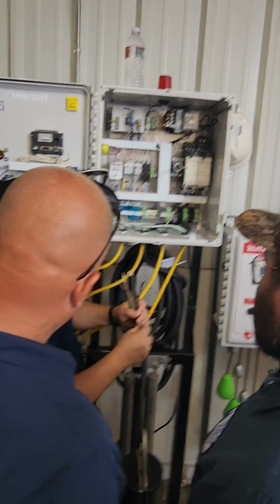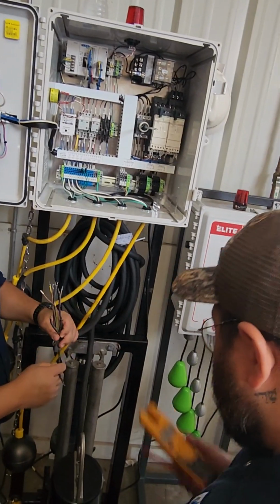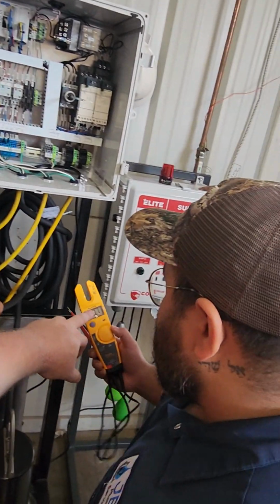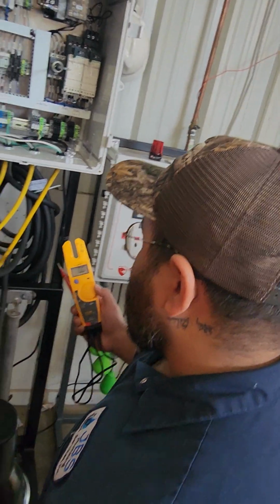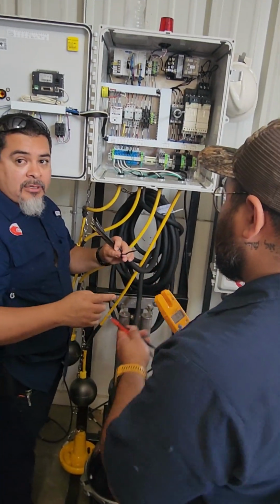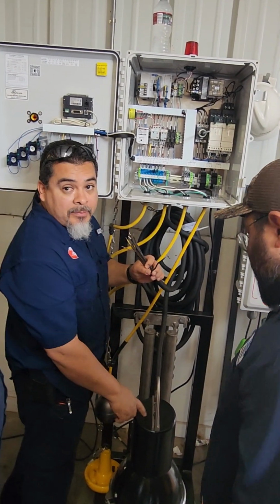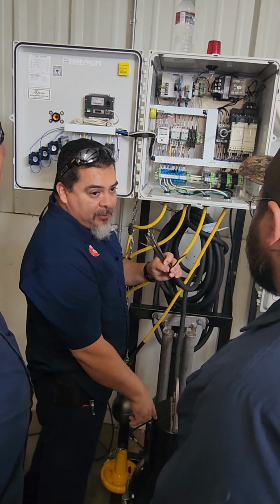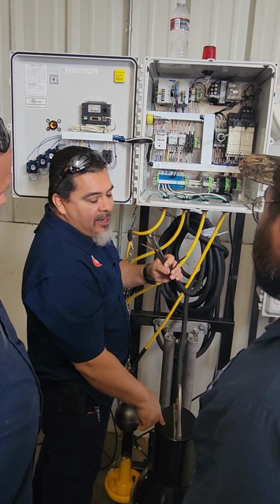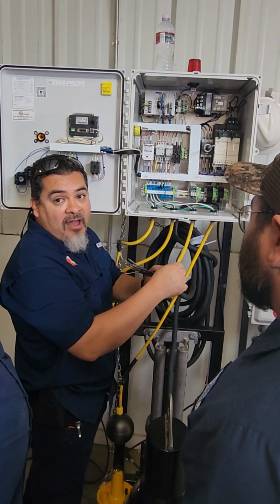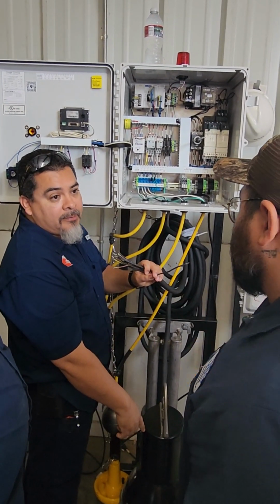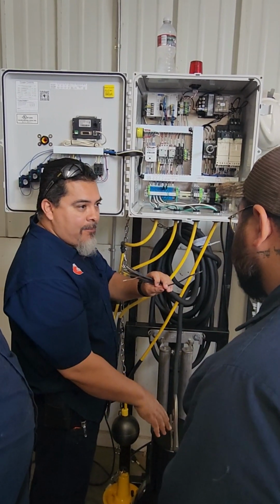All right. So how can you tell if it's bad? What is this meter supposed to do? No, it's not going to tell you that it's bad. It's going to tell you how many amps the pump is running. So say the pump max is probably 8 amps, but you're reading 25. Motor's locked up. Gotcha.